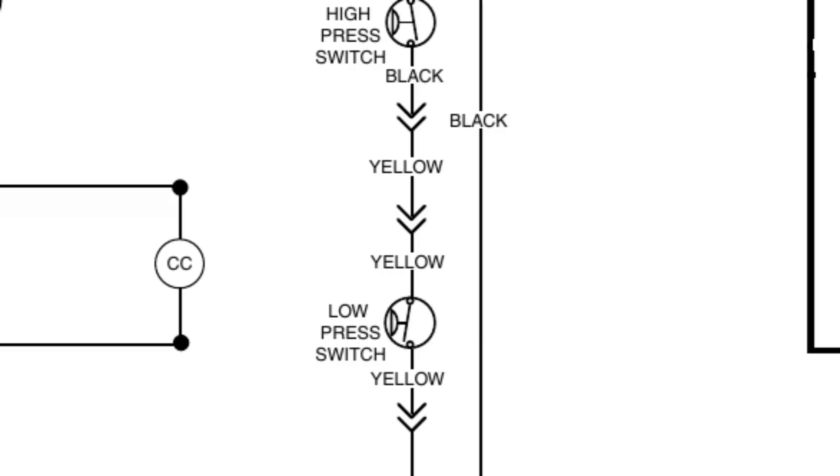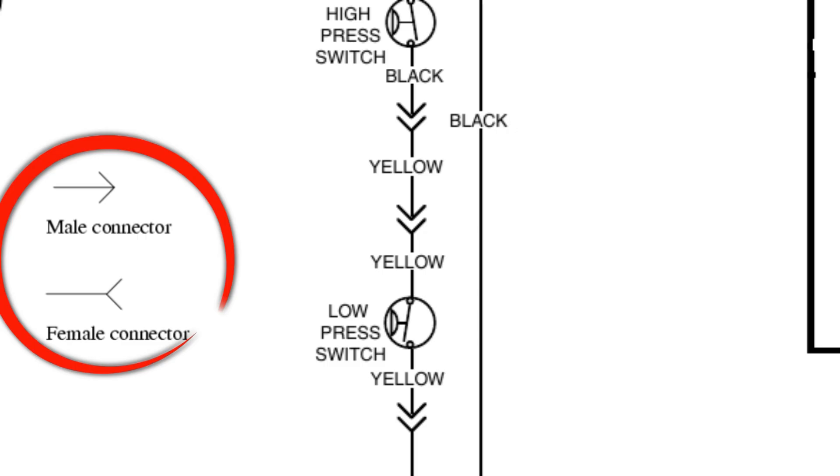Now you're also going to see what looks like arrows on schematics like we see right here. And these are not directional arrows. They're not telling you which way the electricity is flowing or anything like that. What these are, are male and female connectors. So think Molex plugs, things of that nature.